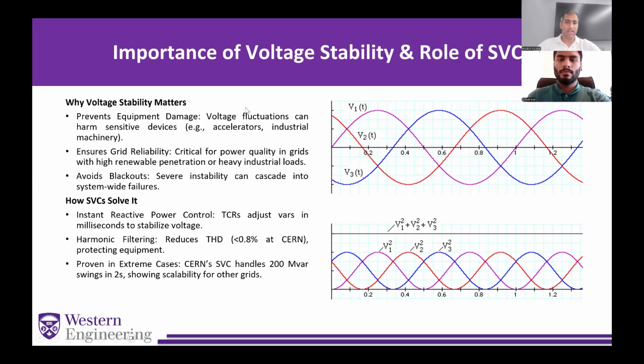So moving on to the next slide, importance of voltage stability and role of SVCs. Voltage stability isn't academic. It's the line between resilient power and cascading failures. When voltage wobbles, sensitive equipment degrades, renewables trip, motors stall, and entire regions can dim to black. SVCs tame that chaos by injecting or absorbing reactive power in milliseconds, filtering harmonics, and as proven at CERN, shrinking brutal Mvar swings into calm, stable voltage windows that keep critical machines alive.